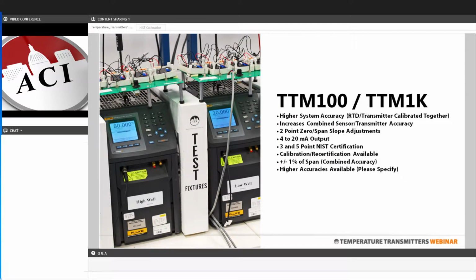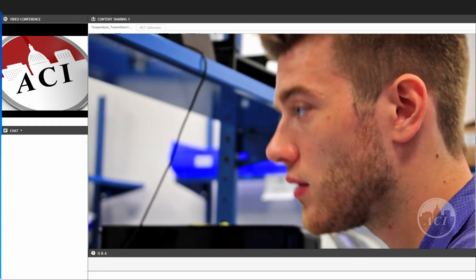We have the ability to do NIST traceability and certification for all of our temperature transmitters. This is something that we're seeing more and more of in recent years, and we expect this trend to continue to grow going forward. And what we do when we NIST certify a temperature transmitter is that we pair an individual sensor to an individual transmitter, serialize that product, and test it in our NIST traceable testing chamber, and then provide documentation for each sensor that this unit on this date and this time passed our testing and falls within the stated tolerances of these temperature transmitters. So here's a short video that shows the NIST testing process.